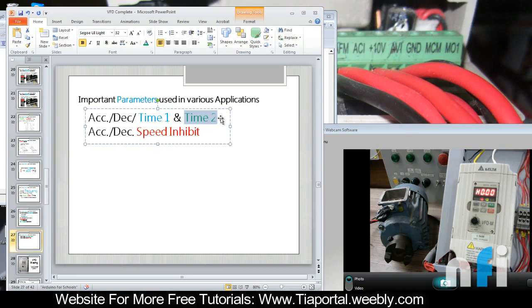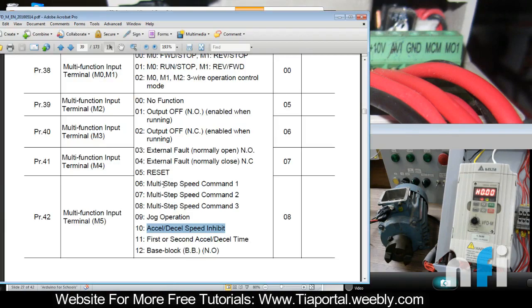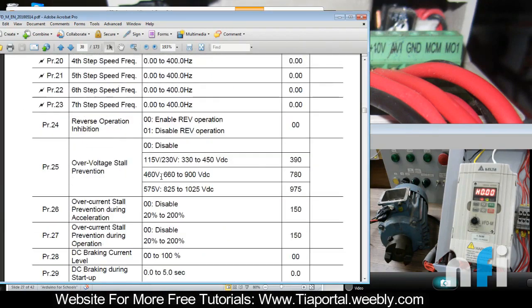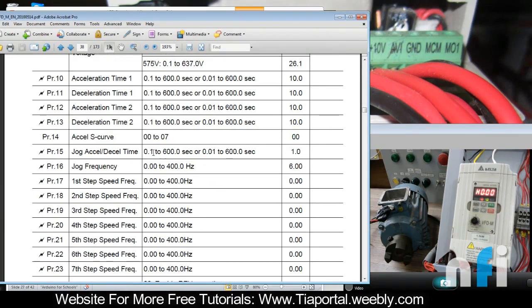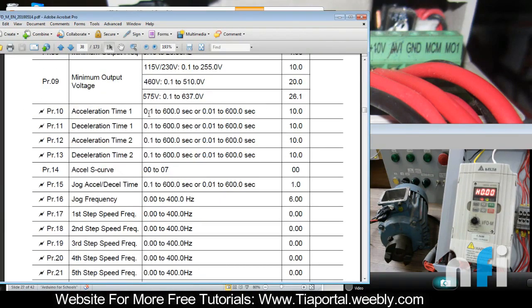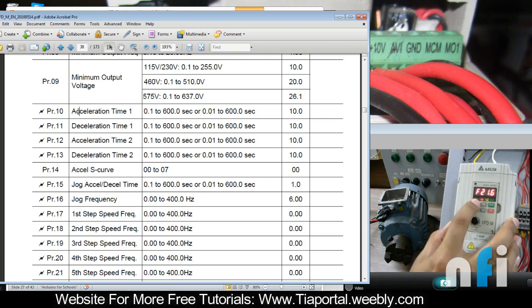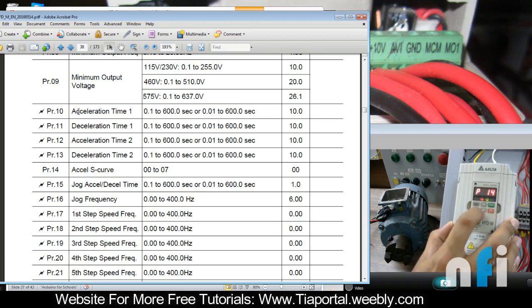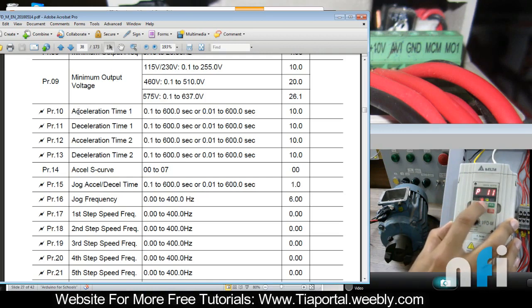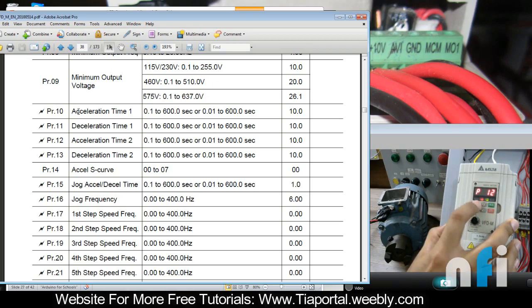In some applications you want the motor to start abruptly to high speed. To do that, we have to first set the acceleration/deceleration time in parameters 10, 11, 12, and 13. Let's see what we have in these parameters. Parameter 10 has 10 seconds, parameter 11 is again 10 seconds, parameter 12 is 0.1 seconds, and parameter 13 is 0.1 seconds.